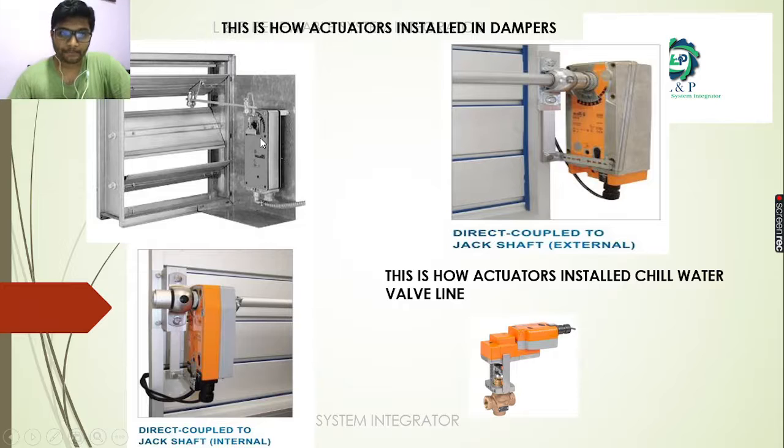Okay, the output of the damper will act as an analog input to the PLC, and the output from the PLC, that is the command from the PLC, will act as an input to these valve actuators. It will be a 2 to 10 volt supply.